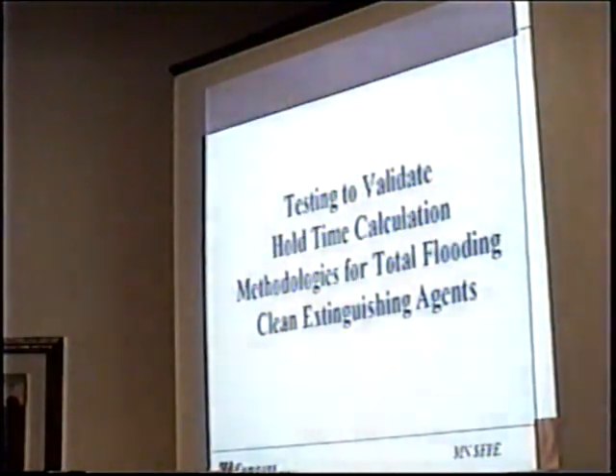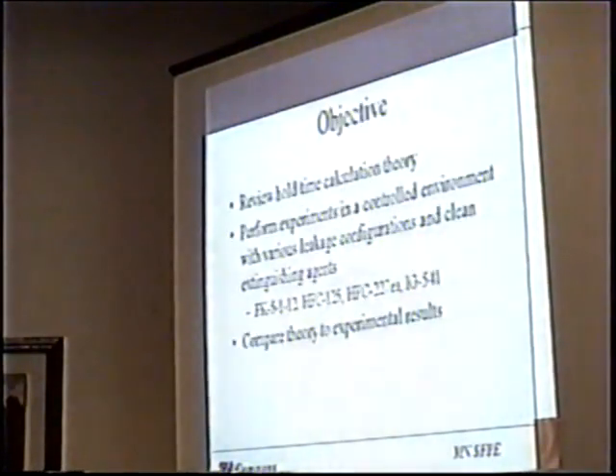The work, essentially, is a validation study. In NFPA 2001 and ISO 14520, they have listed equations that you can use to, say, put in a certain concentration of agent to a certain size room and determine how long it's going to stay in there. Typically, we mandate a 10-minute hold time to provide for extinguishment, initial extinguishment, and fire knockdown, as well as to wait for cool down so that ignition doesn't reoccur, as well as to provide for the arrival of backup manual suppression.